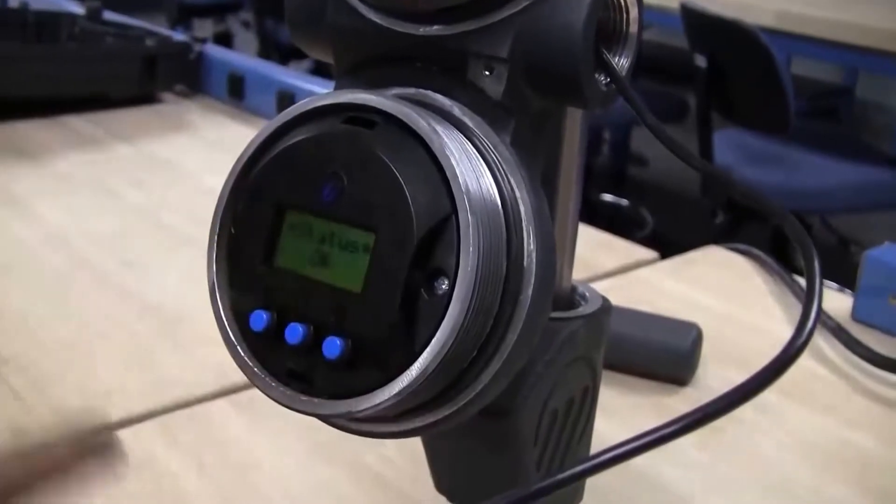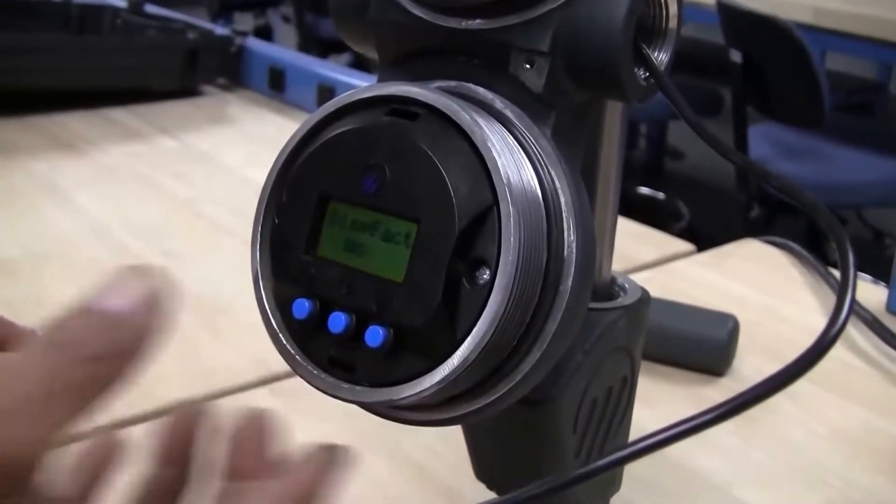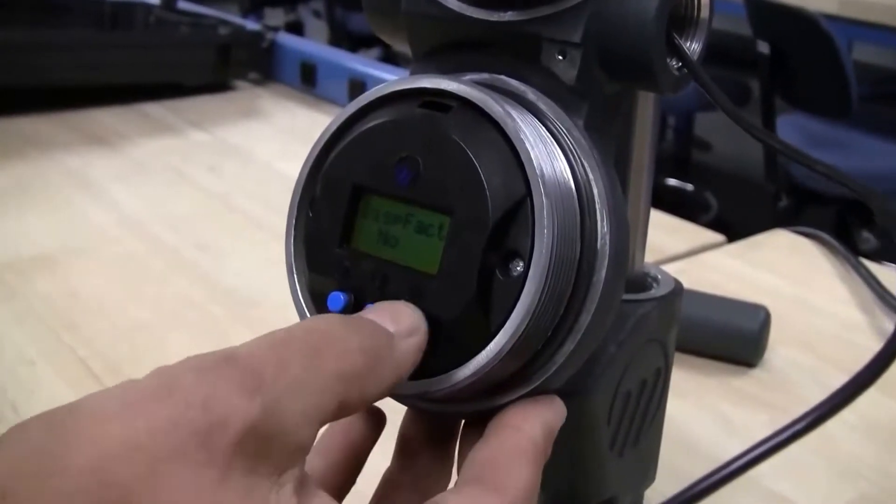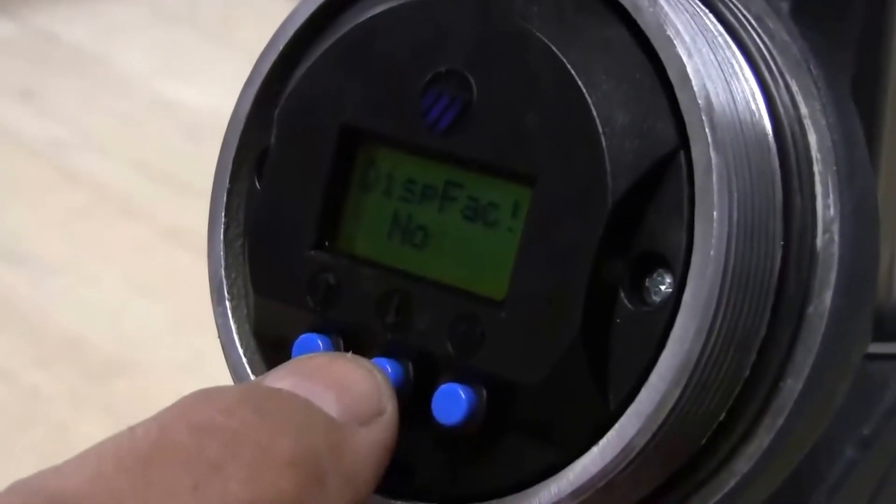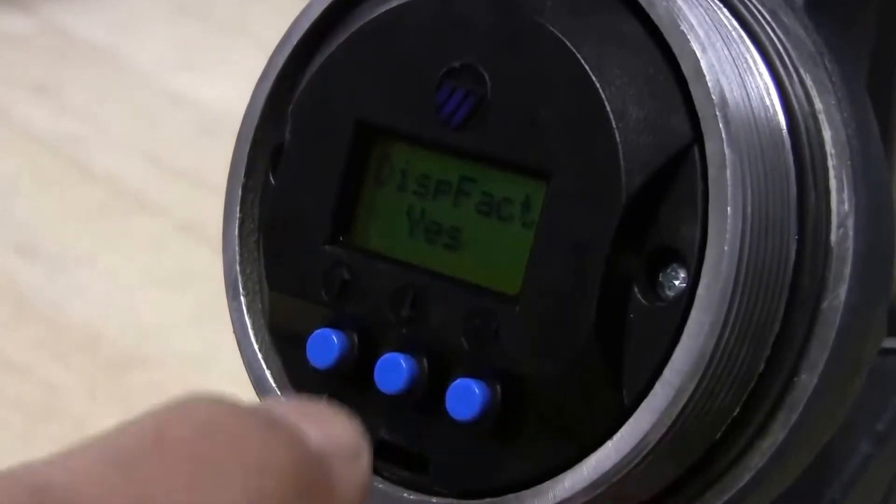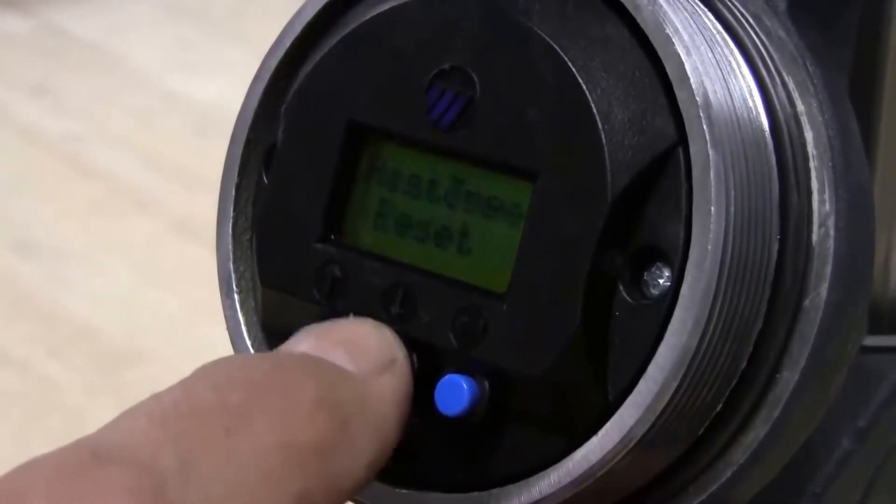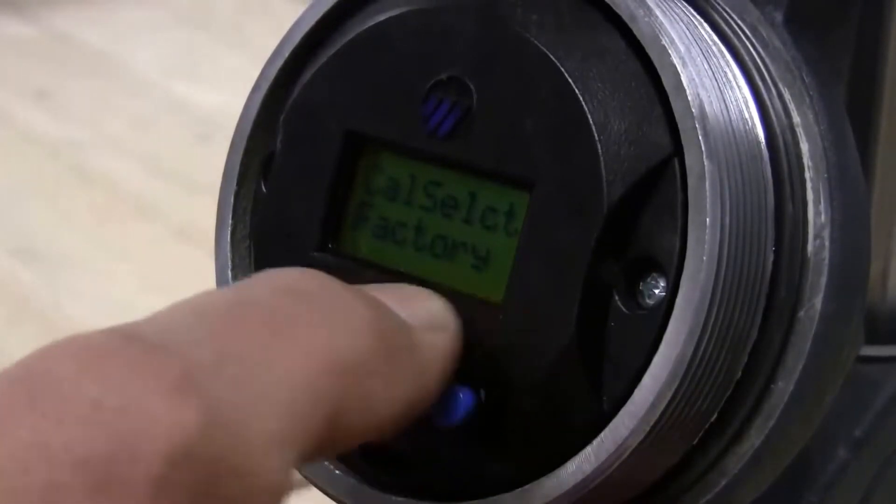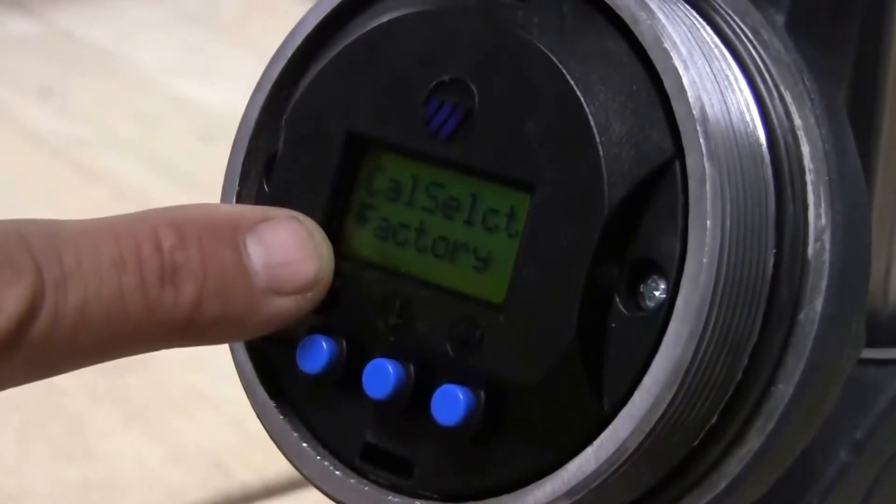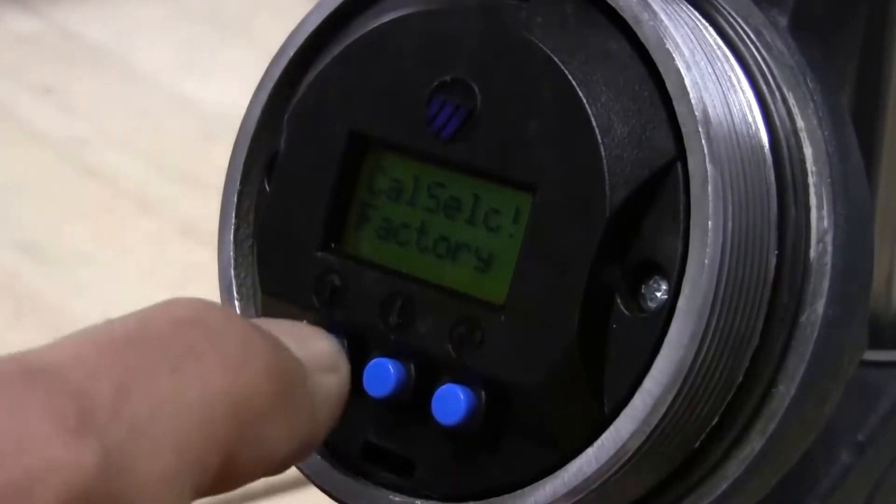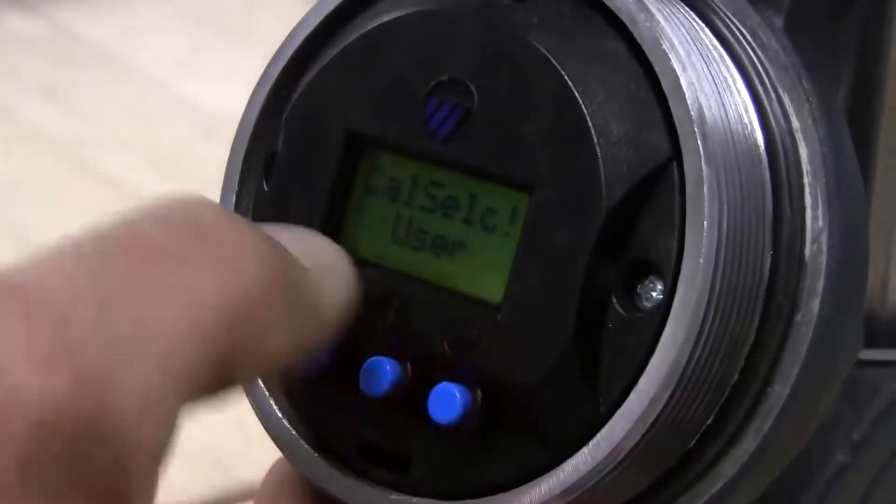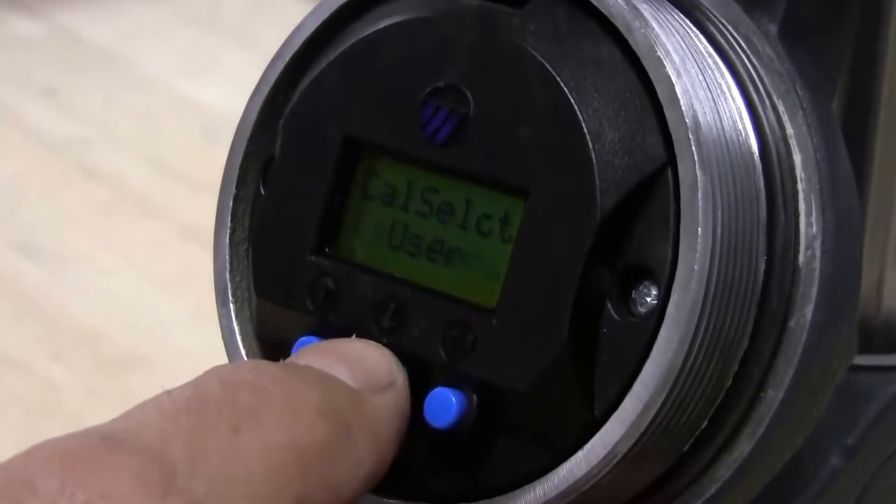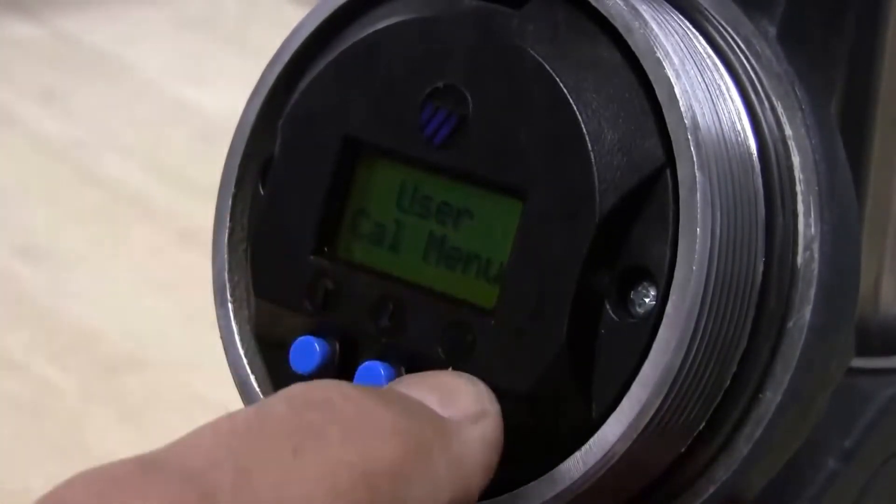From the run mode or scrolling mode here, you push the up key. It's going to say display fact, no. Push enter, and down arrow or up arrow to change no to yes. Push enter. Now scroll down to cal select. It'll say factory. Push the enter key and change factory to user, and push enter. We are now in the user cal mode.